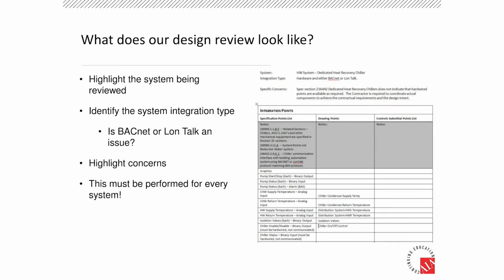But this is what our design review layer looks like. It's simple. It's a spreadsheet, right? It's basically starting to look at a system-by-system evaluation of the entire building, the entire project. Up top we have a system description, and then I have an integration type. This particular one, again, it's a little hard to read, but it says, based on what I read in the specs, integration type was hardware and either BACnet or LonTalk. So that's what this dedicated heat recovery chiller said it would do.